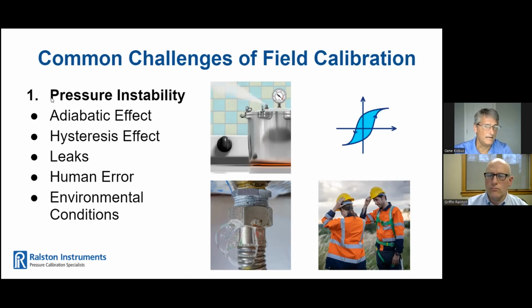Leaks. Even the smallest leak in volume and change in a hydraulic system can lead to noticeable drops in pressure. Whether it's a poorly thread-taped connection, a damaged seal, a loose connection, or another issue, leaks decrease the volume of fluid within the system. As a consequence, the pressure from the hydraulic fluid diminishes proportionally. A single drop of fluid leak can cause a pressure drop of 500 psi or more.